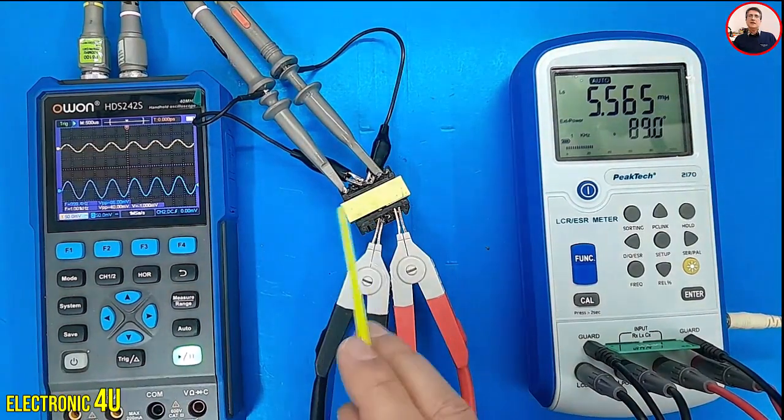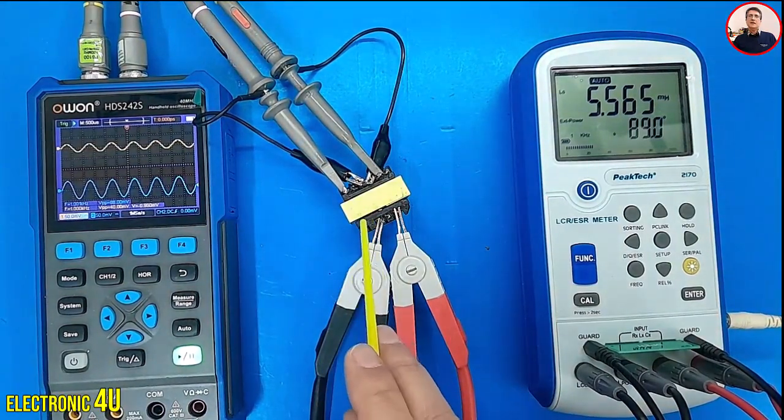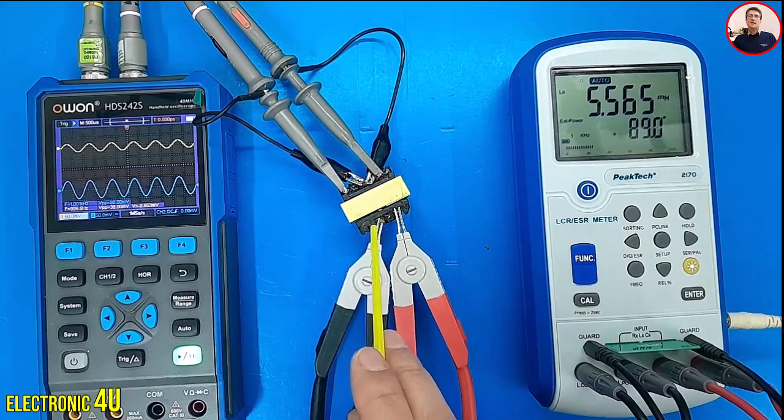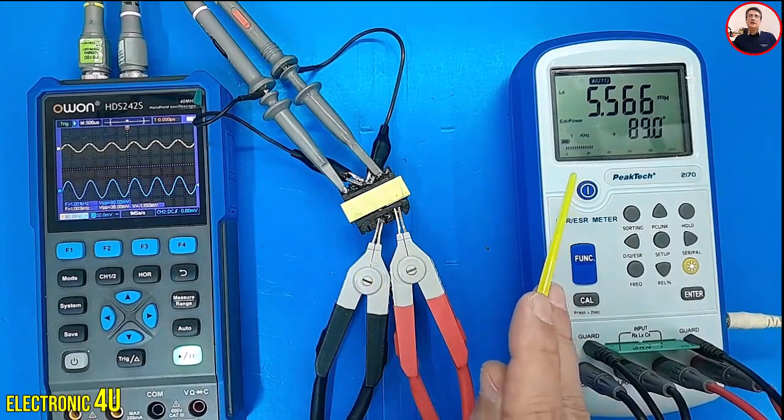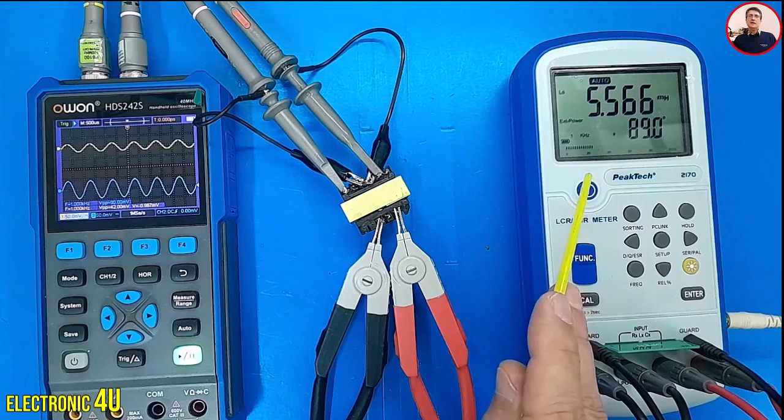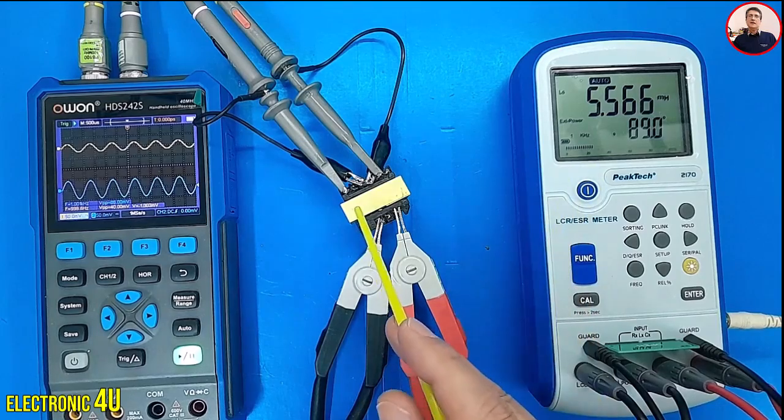So, by this method, we can ensure the transformer works by injecting a signal into the input or output winding and checking the phase angle. This number should be close to plus 90. Then, by shorting the winding, we check the phase change.